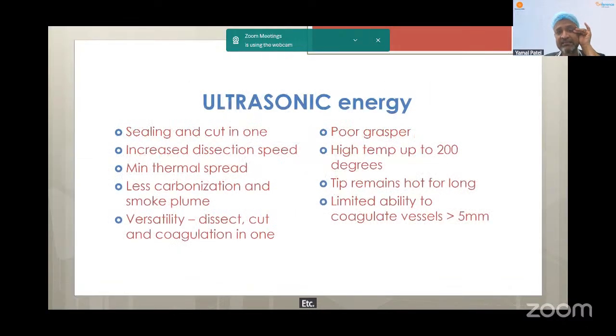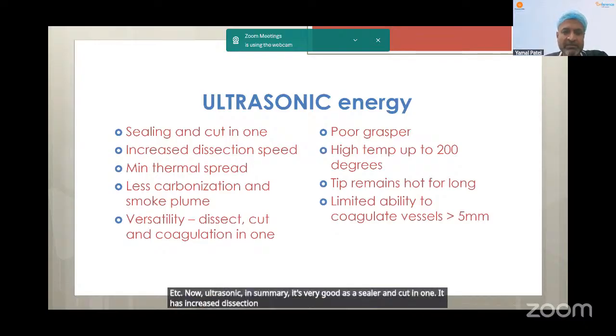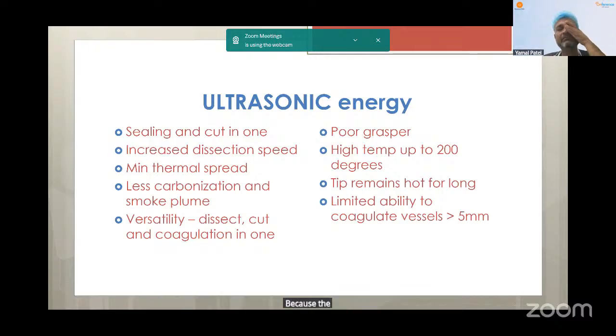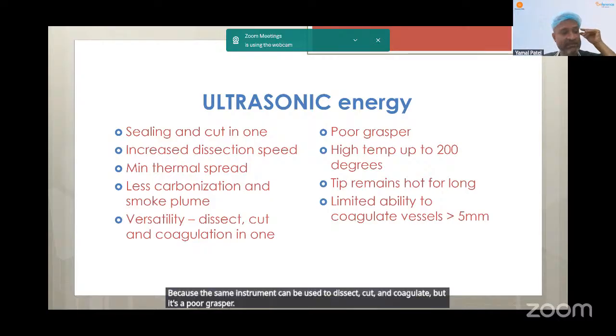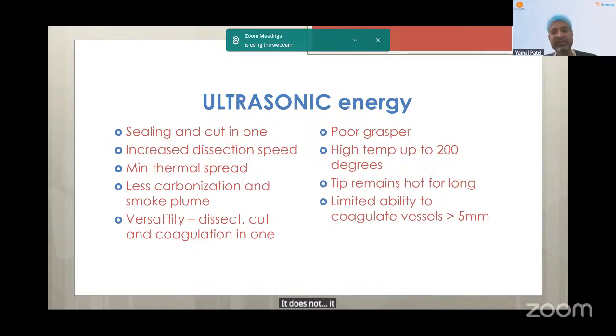Now, ultrasonic, in summary, is very good as a sealer and cutter in one. It has increased dissection speeds with minimal thermal spread, less carbonization and smoke, and it's very versatile because the same instrument can be used to dissect, cut, and coagulate, but it's a poor grasper. It goes very high in temperature, up to 200 degrees, and the tip can remain hot for long, and it can be used less in vessels above 5 millimeters.